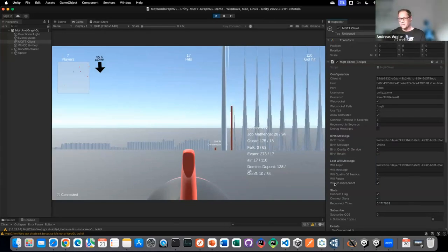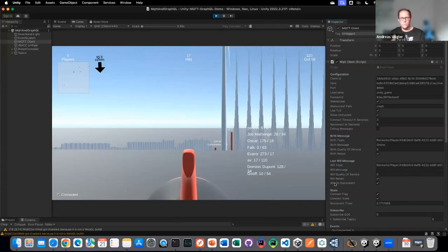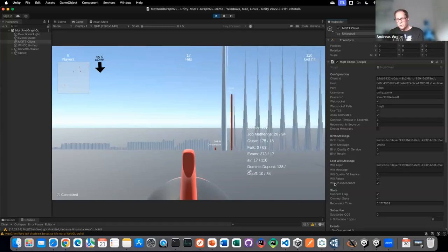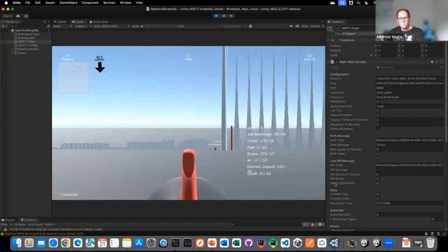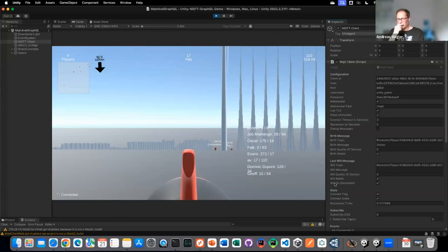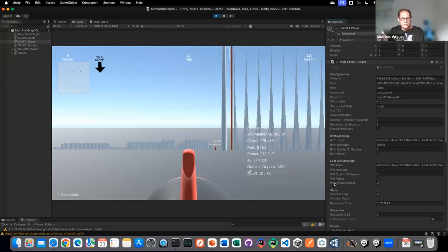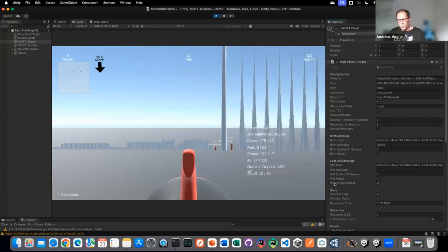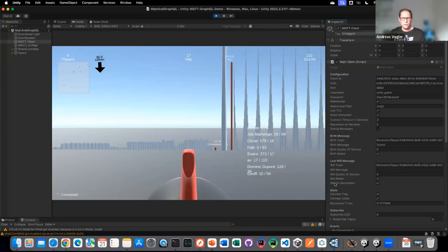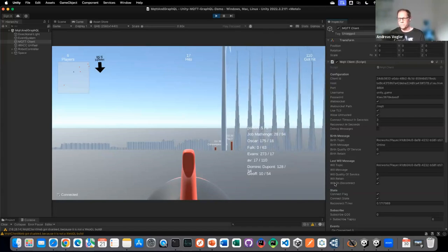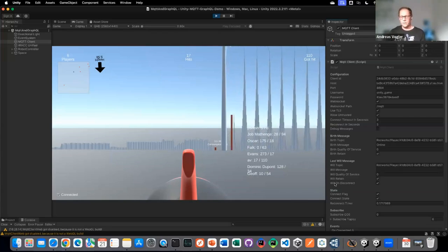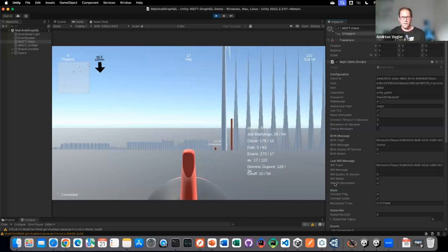And I mean, OPC UA has also a lot of benefits because it is well defined. You have a well defined structure. You have metadata in it. And on MQTT, for sure, you can also build all this, but basically it is data agnostic. So you can use your own format. I mean, this is a big plus on the one hand. On the other hand, it is also a drawback because everyone creates his own format and then no one can communicate together anymore. But we have Sparkplug B. Maybe this will help. At the end of the day, I would say both will be there and will stay there. So I don't think that one will eat the other one.